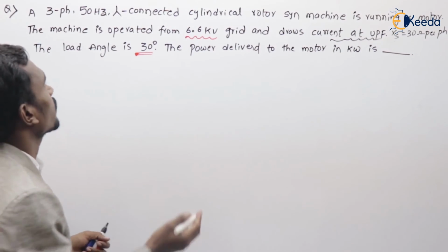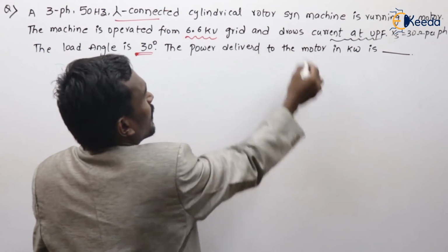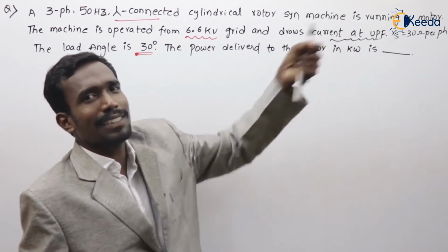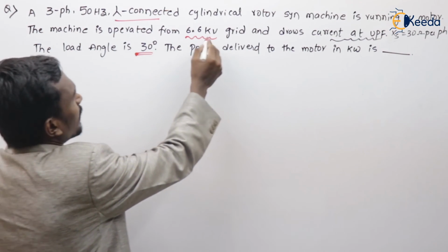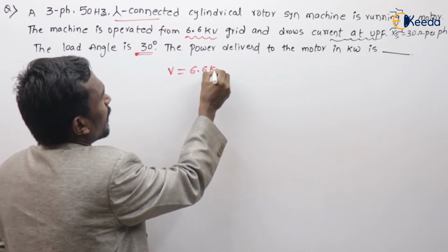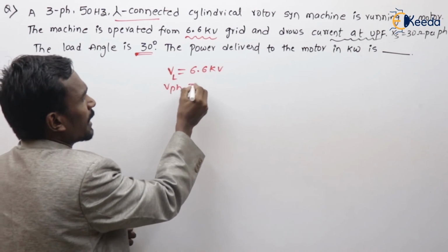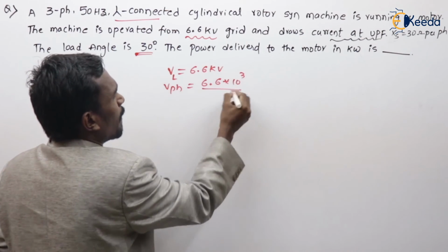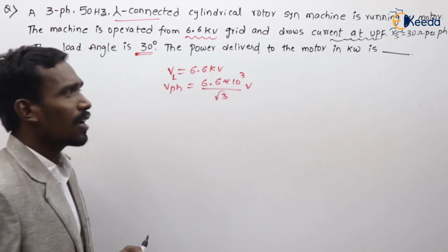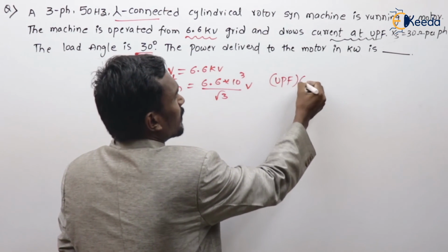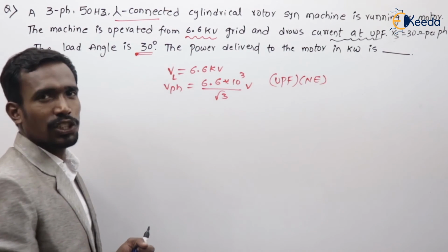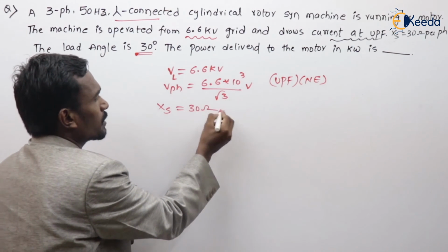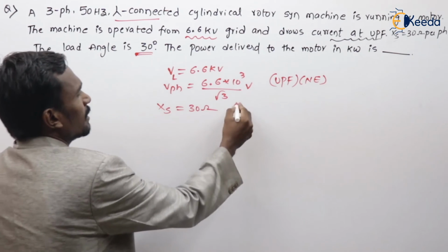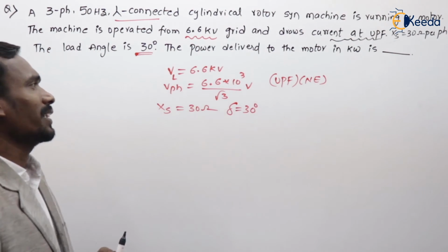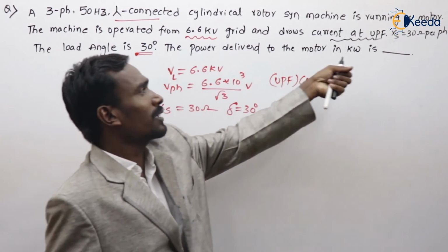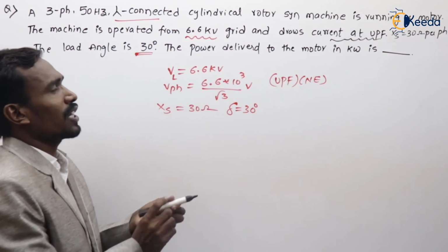Right, next question. See here. A 3-phase 50 Hz star connected cylindrical rotor synchronous machine running as a motor, operating from 6.6 kV. This is the line voltage. What is the phase voltage? 6.6 into 10 cube by root 3 volts is the phase voltage. And they gave unity power factor, nothing but normal excitation. They gave XS per phase 30 ohms and load angle 30 degrees. Now we have to find the power delivered to the motor in kilowatts.